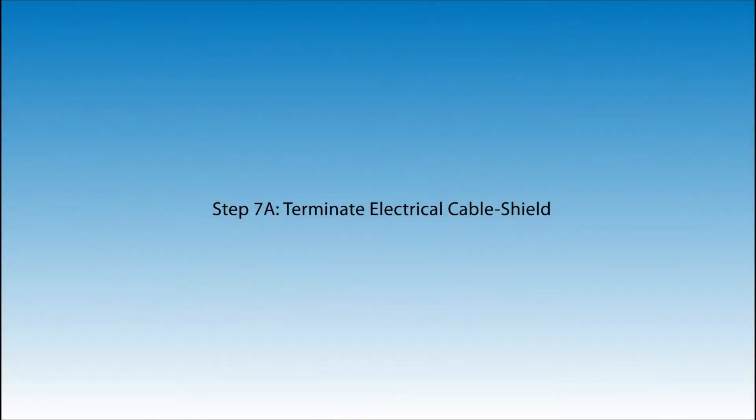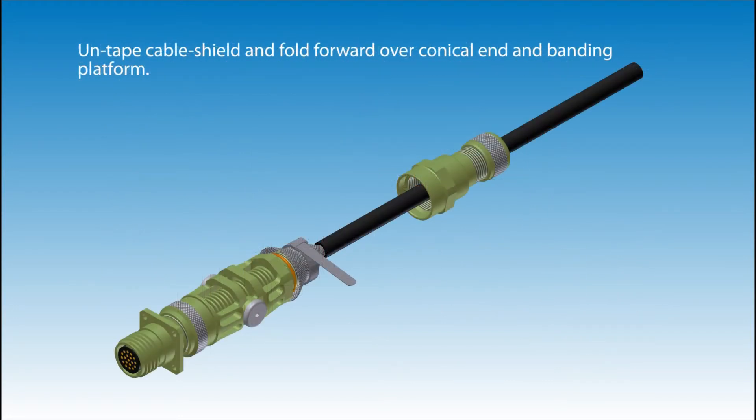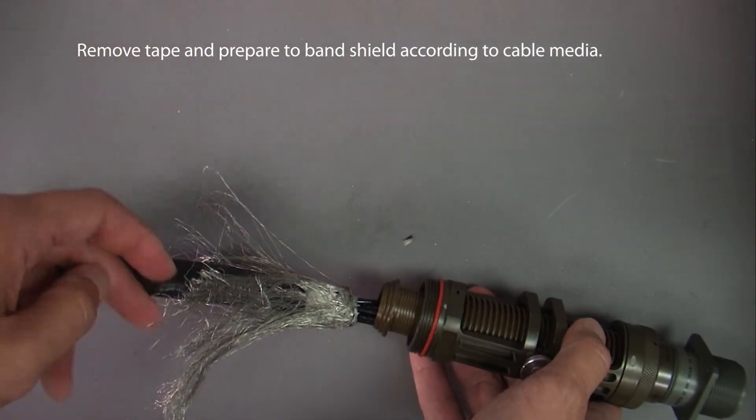Step 7A: Terminate electrical cable shield. Jacket should measure 3/8 of an inch from the conical end of the main back shell body assembly to the cable jacket. The service loop length is contained inside the back shell. Untape the cable shield and fold forward over conical end and banding platform. Complete band termination, ensuring cable jacket remains 3/8 of an inch from the conical end of the main back shell body. Remove tape and prepare to band shield according to cable media.